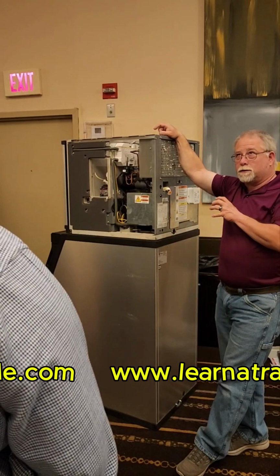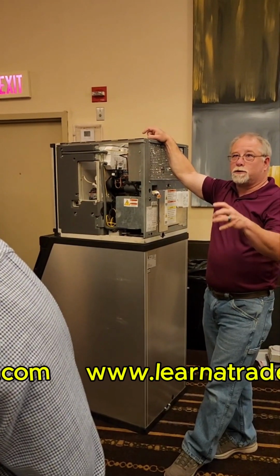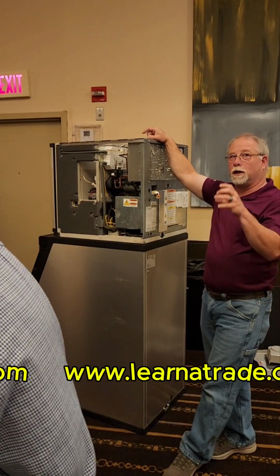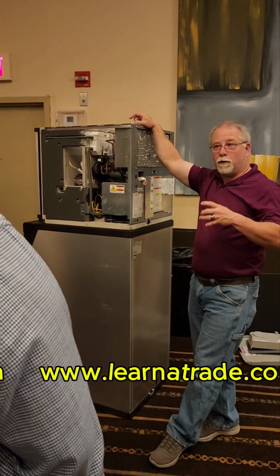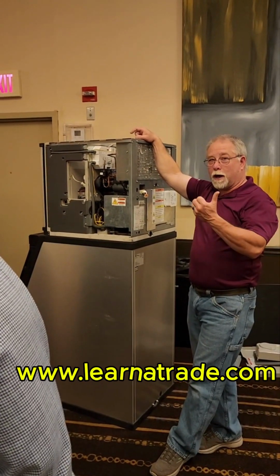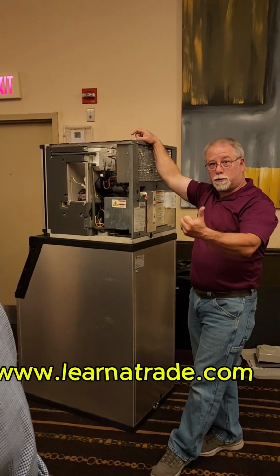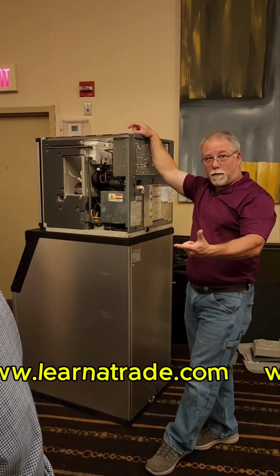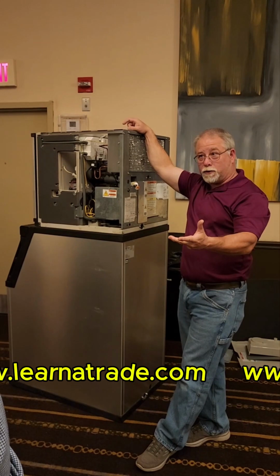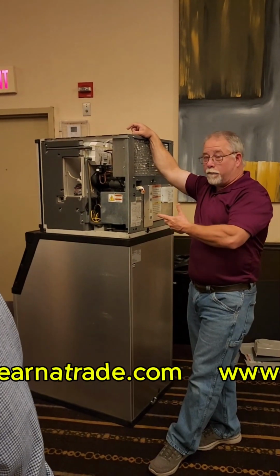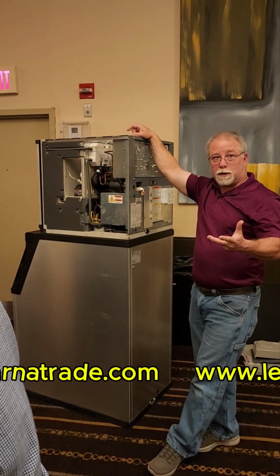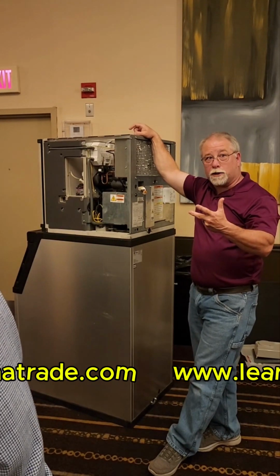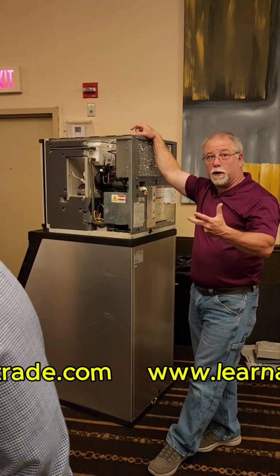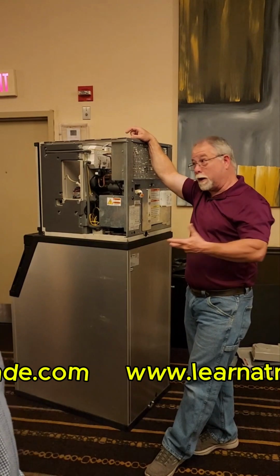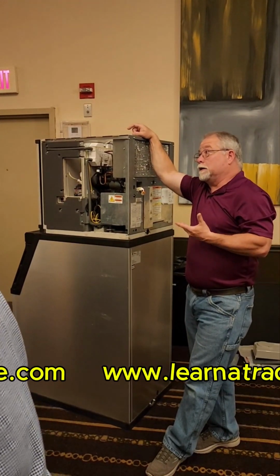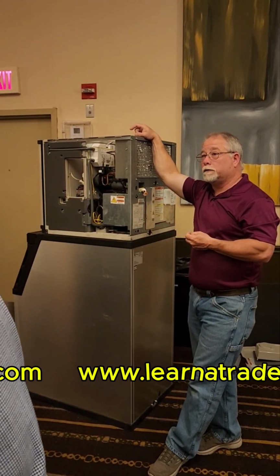We don't use pressures, temperatures, superheat, subcooling. When you're talking to us on the phone about what a charge should be, we'll ask: do you have OEM components? Did you pull a 500 micron vacuum? Did you weigh in the factory charge? Every one of our techs on tech support, those are the 3 things we'll ask. If you haven't done those, that's what you're gonna do before we talk about anything else. It's just the way we are.